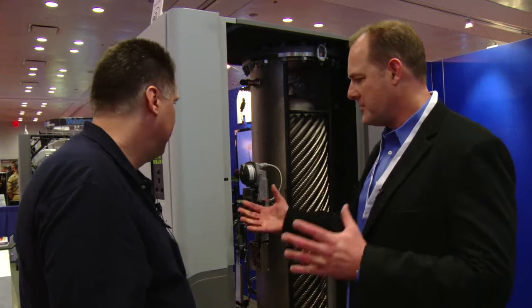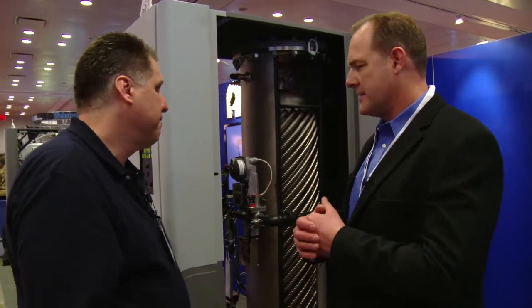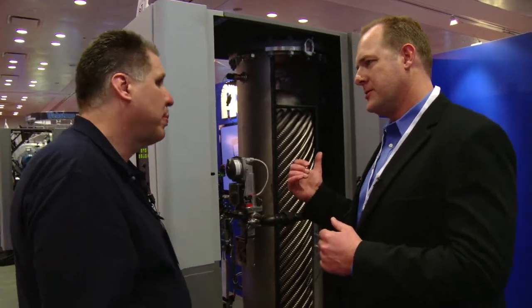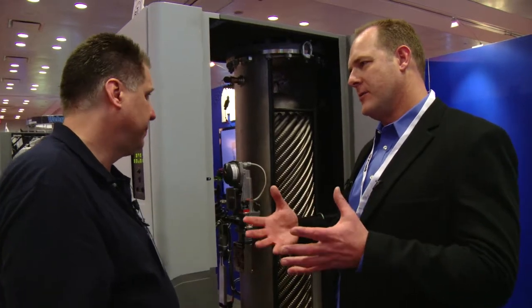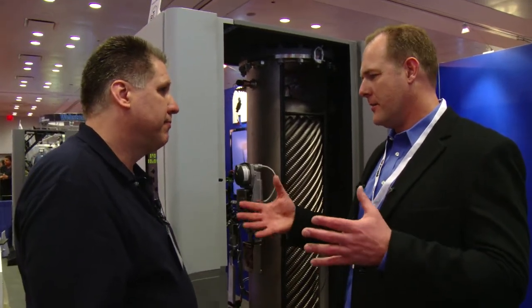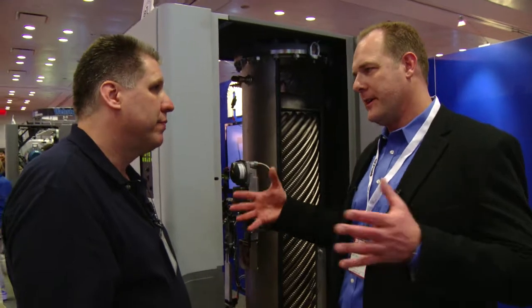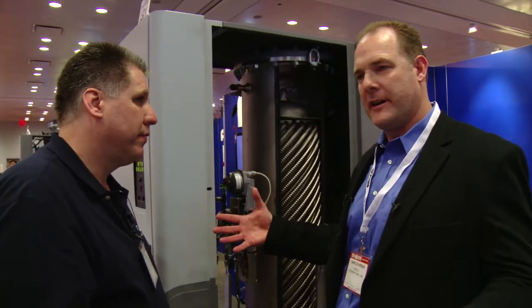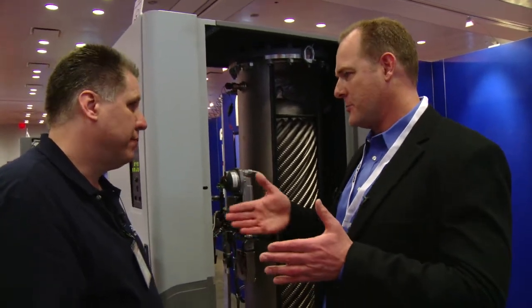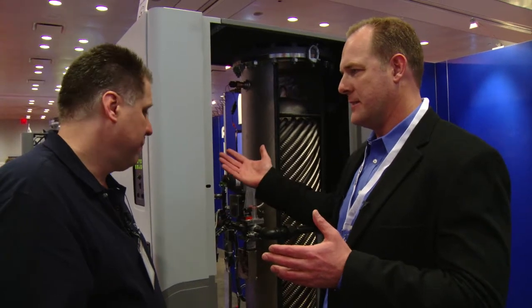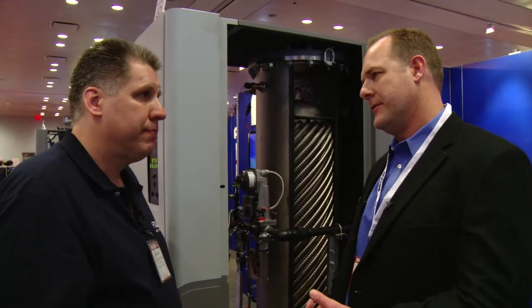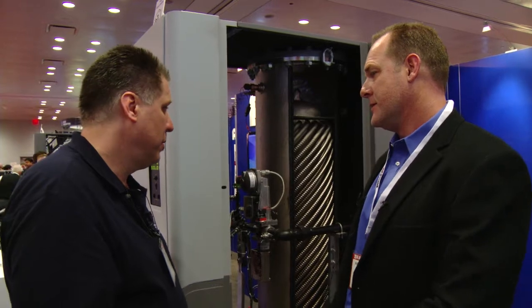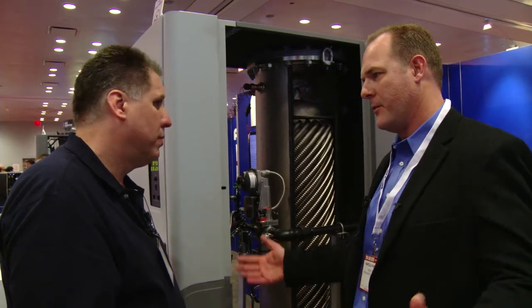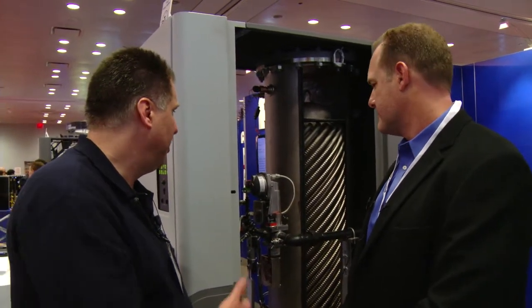Exactly. In fact, when we do bank multiple units together, typically there will be a control valve on each heater. So for instance, in a hotel application where you have a very small load, you might have 3 out of the 4 heaters isolated from the system and only 1 operating. As the load increases, we would add heaters based on the capacity demands of the building. So it really saves a lot of energy and offers that redundancy when you have to service 1 heater for a commercial application.